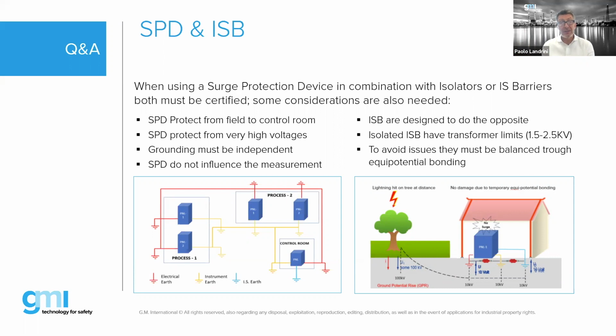The grounding, this comes back to the same question we had earlier: all the grounding must be independent, and to avoid any grounding floating issues, they have to be equipotential. So the grounds that you might have, the IS ground, the SPD ground, the electrical ground, they all have to be independent and go to a ground rod, but to avoid any raising of the voltage between the grounds, you have to make them equipotential. This is very difficult to have at different locations, so there exist devices that allow this. There are switches which will temporarily make the ground equipotential in case of a high voltage, in case of a fault. I hope I answered that.